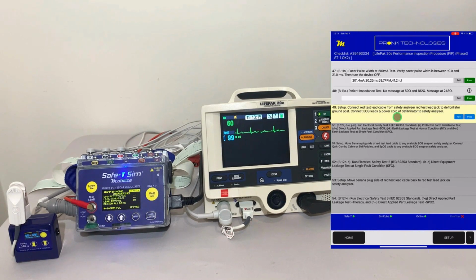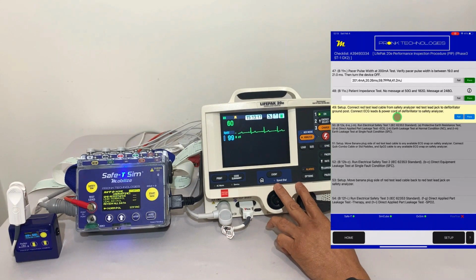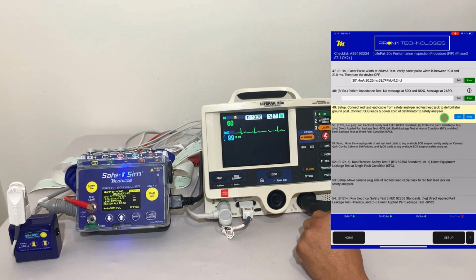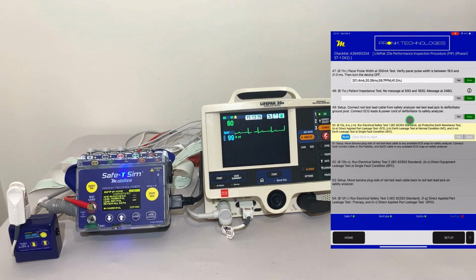So in the manufacturer's procedure, it requires us to do the electrical safety testing according to the IEC 62353 standard. So we're going to go ahead and follow what that standard requires. Of course, what standard you follow could vary depending on your company or organization's protocols. Some customers follow NFPA protocols, which are common, or you can follow exactly what the manufacturer requires per the manual, which is what we're going to do here.